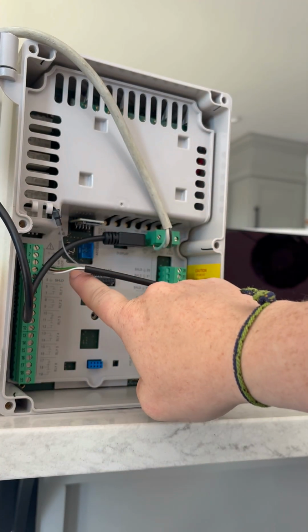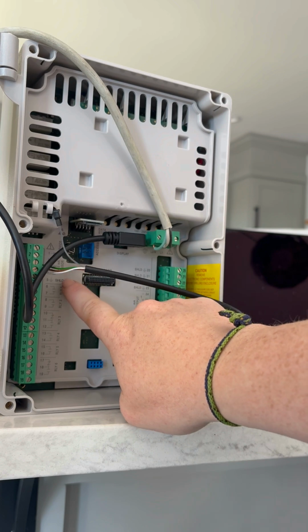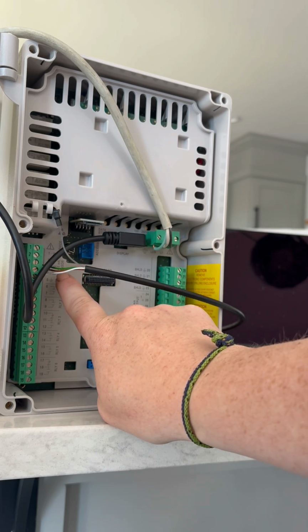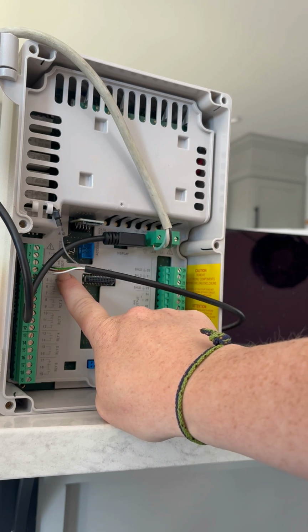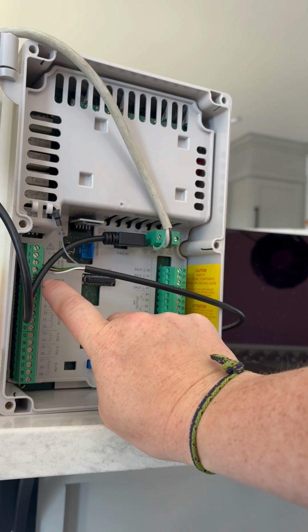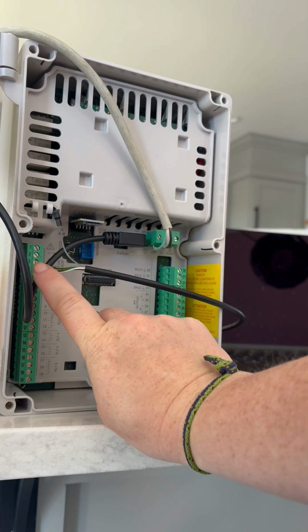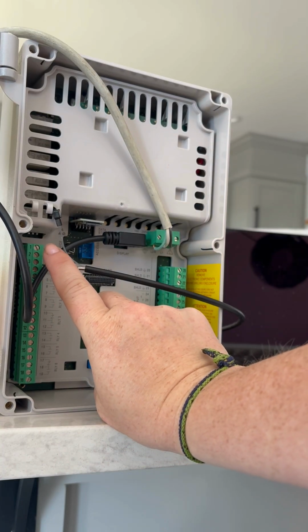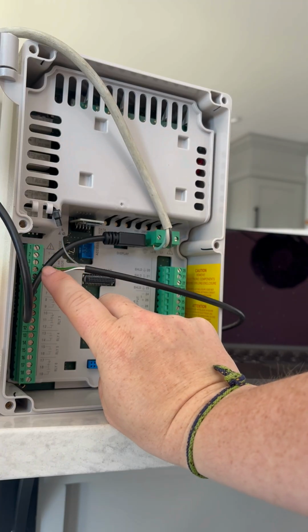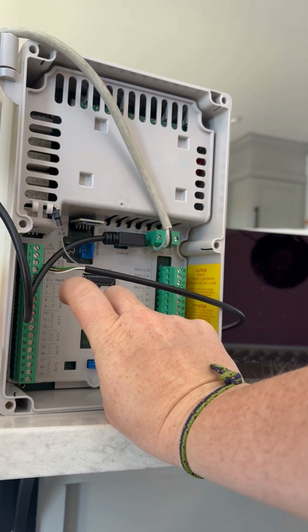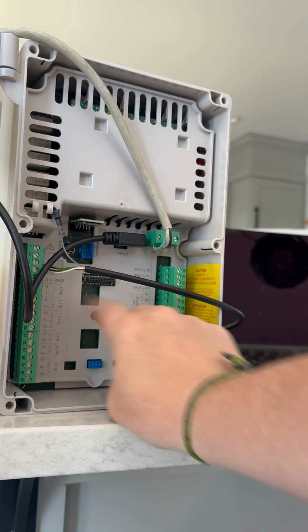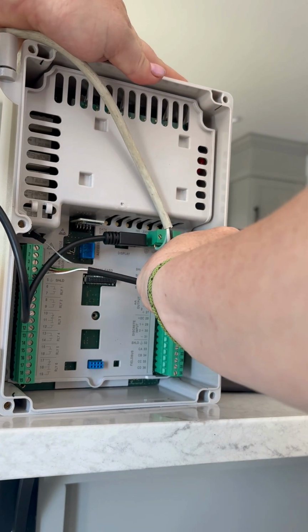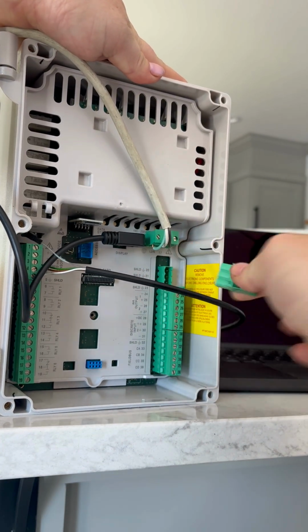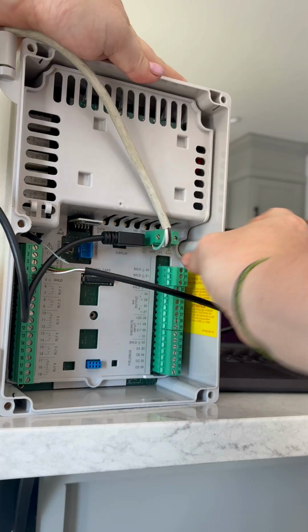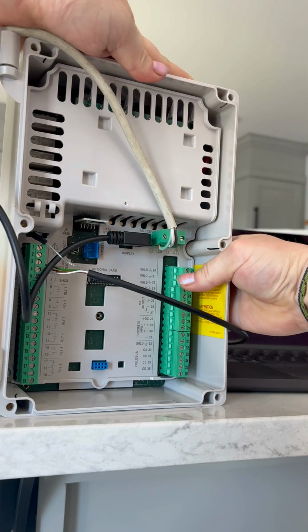Also, when you're wiring up, if you have one sensor, you want to make sure you go on the lower terminals, so that's 3, 4, and 5. I know it's kind of counterintuitive, but sensor 2 is actually on the top. Just something to be aware of. It is marked here as well, and all these terminal blocks are removable, so you can just pull them out and install them back in.